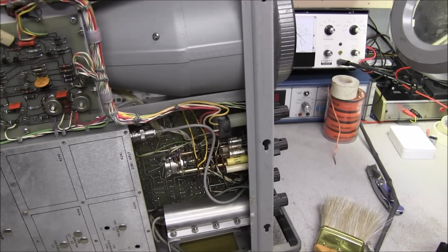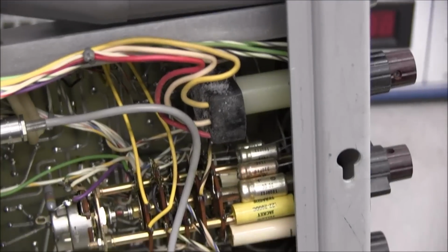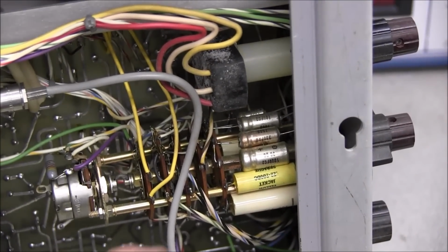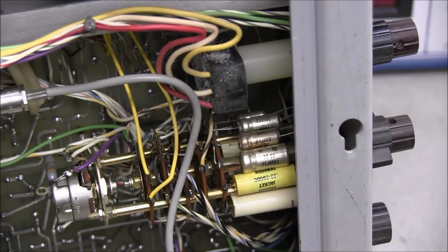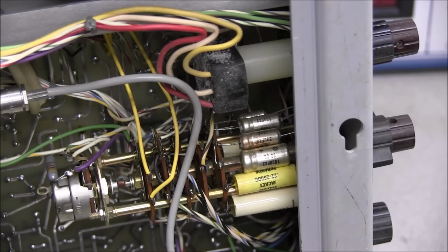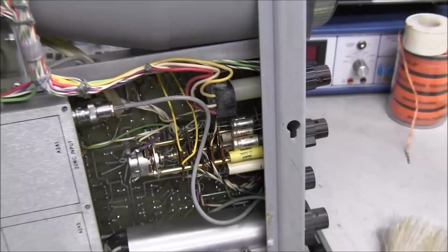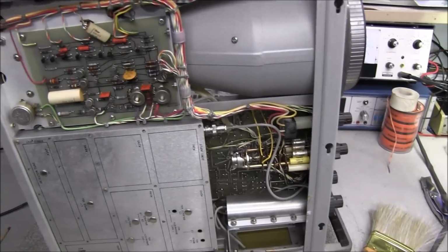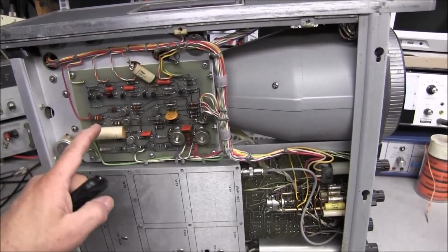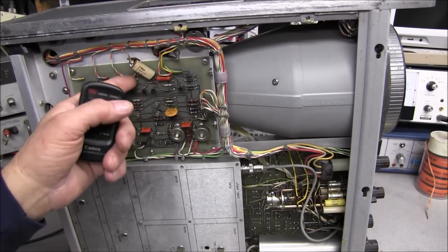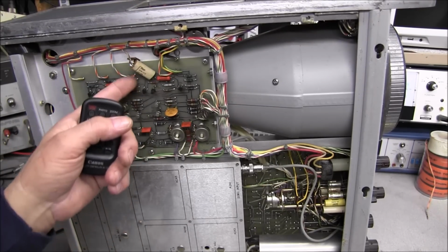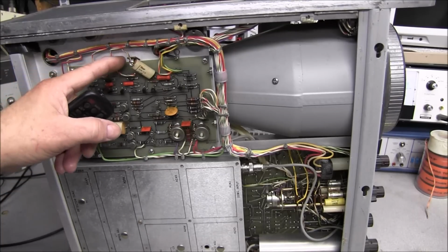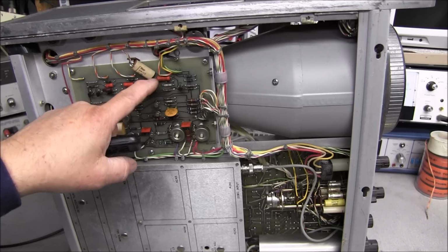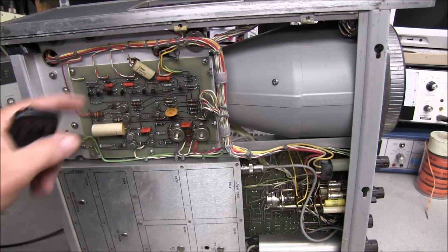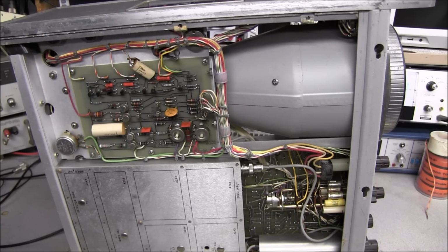And if you notice on the back of that sweep range control, it's got a ton of capacitors around it. All those will probably have to end up being replaced. You know, as old as this thing is, we can see a few capacitors up on this board. This one looks like it's kind of barged in. They have a single point terminal strip between the circuit board and here with this one cap in it. Probably needed a cap to feed something, so they just barged it in with a terminal strip.